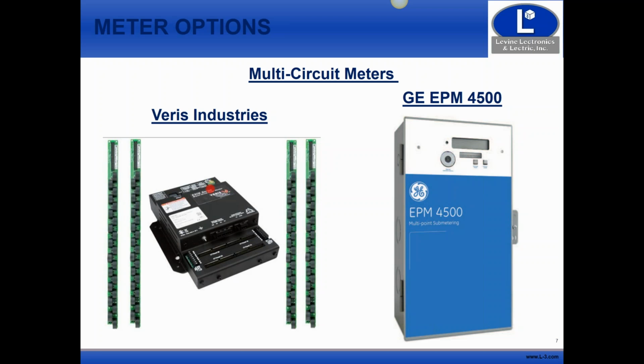If each one of those 20 panels now has one of these Veris Industries multi-branch monitors on it, now we're down to 42 per panel times 20 that we have to go in and program. And we have to tell the system that this circuit on this panel is lighting load, this circuit on this panel is receptacle load. So from a programming and commissioning standpoint, there's a lot more time that has to go into doing this, which adds up to a lot of money in the end.